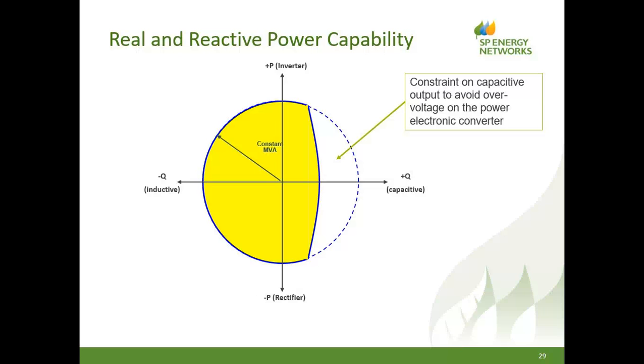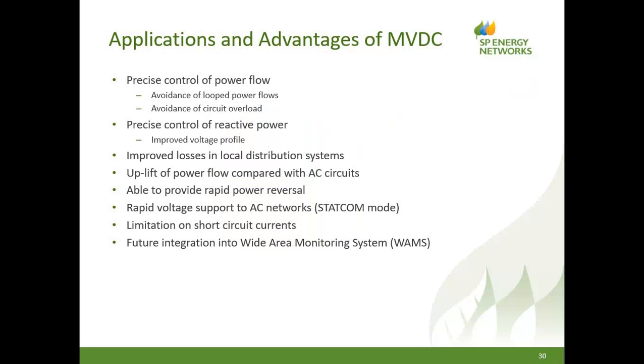If we move on to the next slide. So just to give some of the applications and advantages of this DC technology, we have precise control of power. As Kevin mentioned, we will avoid loop power flows coming from the 400 kV from the nuclear station. So the megawatts that flow in a DC circuit are exactly as required by the operator or by automatic control. It cannot be increased or decreased inherently. It is a controlled flow of power. It also means the system cannot be overloaded.